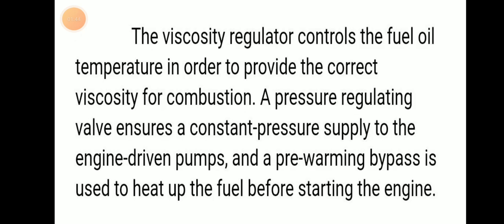The viscosity regulator controls the fuel temperature in order to provide correct viscosity for combustion. The pressure regulating valve ensures constant pressure supply to the engine driven fuel pump.